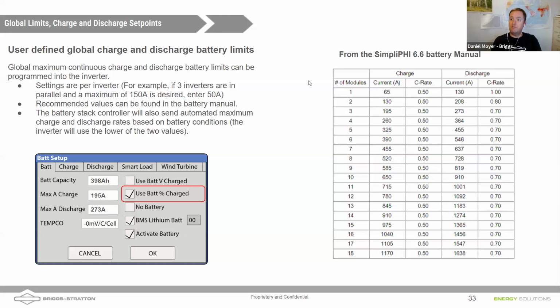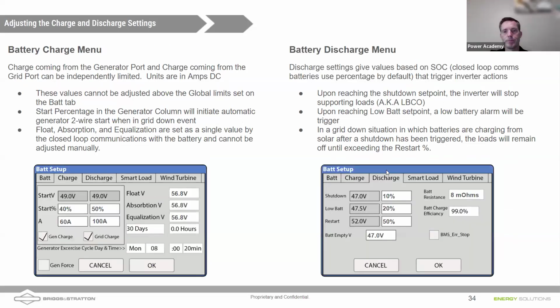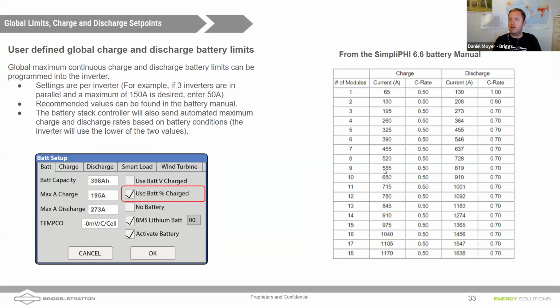Yeah, and we were working on a system with 9 batteries yesterday, a really large, cool system, 585 amps. I will mention that the most you can set is 275. That would be the limitation on the solar. And if you parallel multiple SolarArcs, keep in mind that it's per inverter. So the SolarArc will only allow you to charge up to 275 amps DC, as Daniel mentioned.